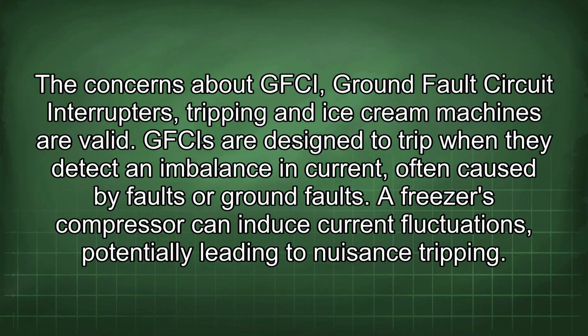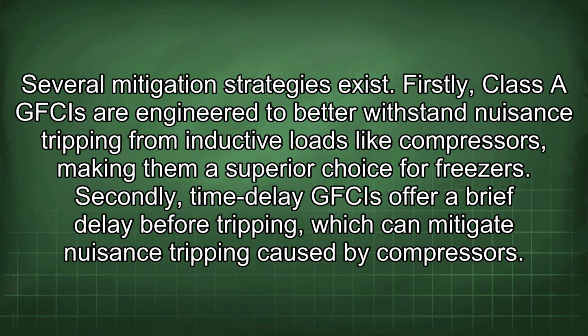Concerns about GFCI, ground fault circuit interrupters, tripping and ice cream machines are valid. GFCIs are designed to trip when they detect an imbalance in current, often caused by faults or ground faults. A freezer's compressor can induce current fluctuations, potentially leading to nuisance tripping. Several mitigation strategies exist. Firstly, Class A GFCIs are engineered to better withstand nuisance tripping from inductive loads like compressors, making them a superior choice for freezers.